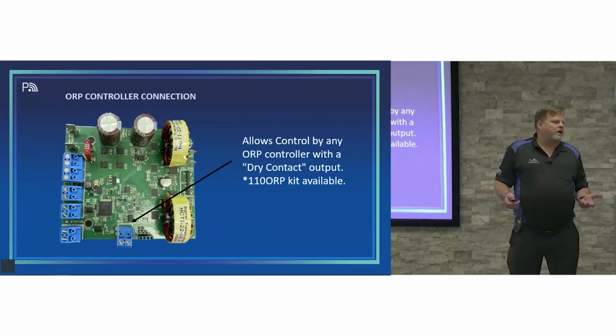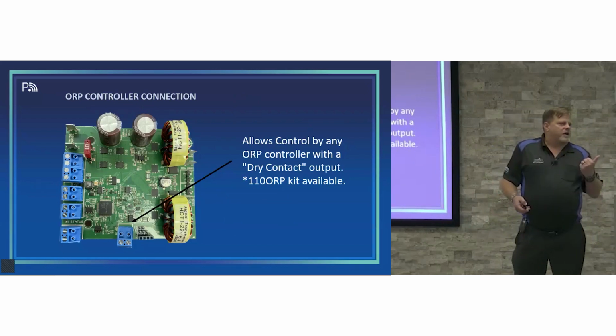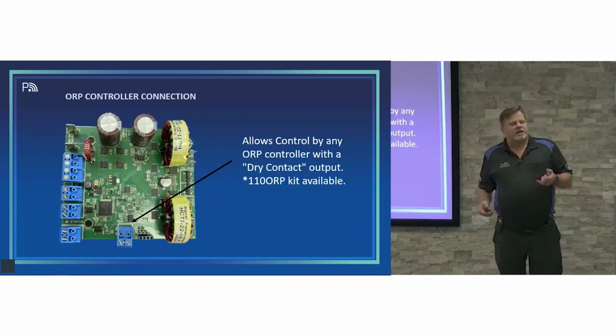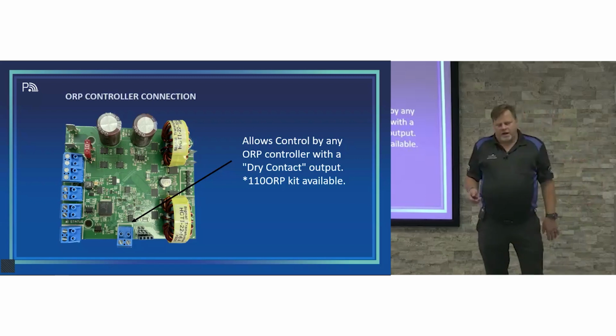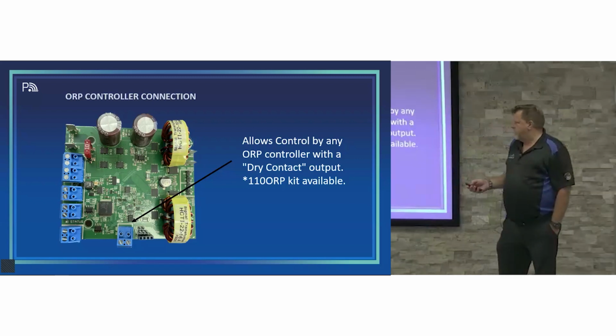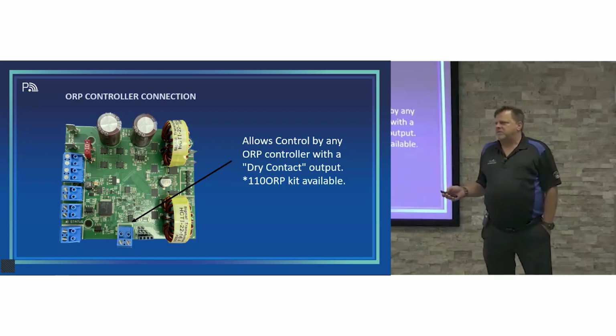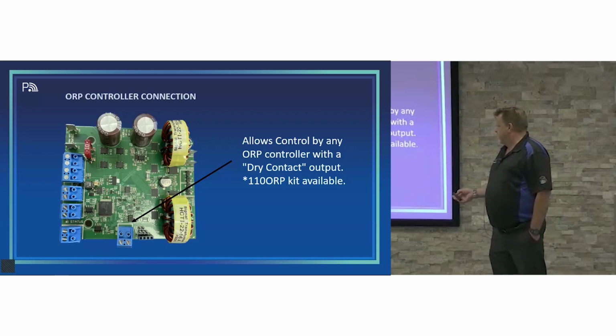When controlled by ORP, if it's controlled by a cat controller or something like that, the ORP drops below the set point. It's going to complete a low voltage signal telling the system, hey, turn the cell on. The cell is going to be at 100% output till it satisfies the ORP. Once the ORP is satisfied, the signal is then open and it'll shut the cell off. And I believe the display says ORP on on the actual display for the PoolSync.